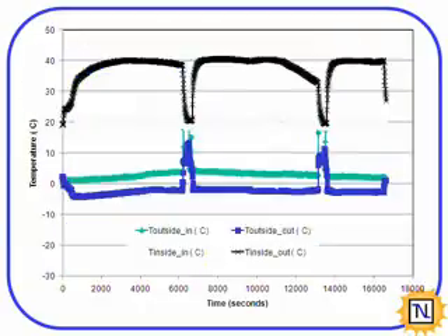These are the temperatures. So we see just above freezing here is the outside air, and it's removing some heat, so it's coming out colder. And we're putting about 40-degree air into the conditioned space. Once again, these are the defrost periods here. What we did in this control, and there's a few ways to do this, is took the air side air in and put that over the evaporator, warming it up. And this time period was maybe from 5 to 10 minutes is what it appears it's going to take to do that.